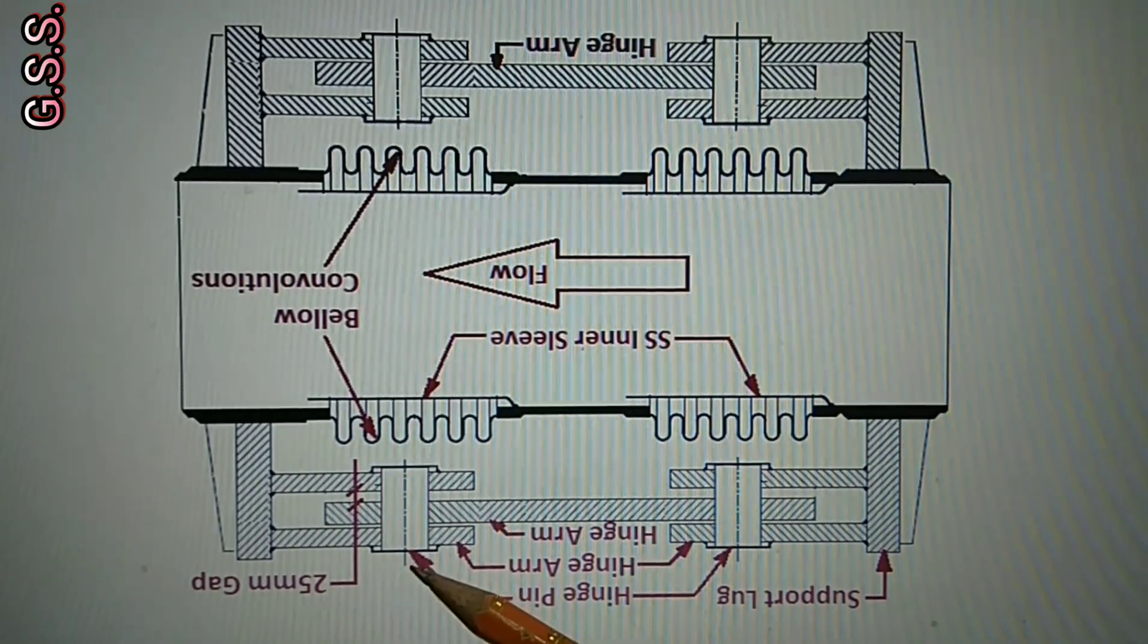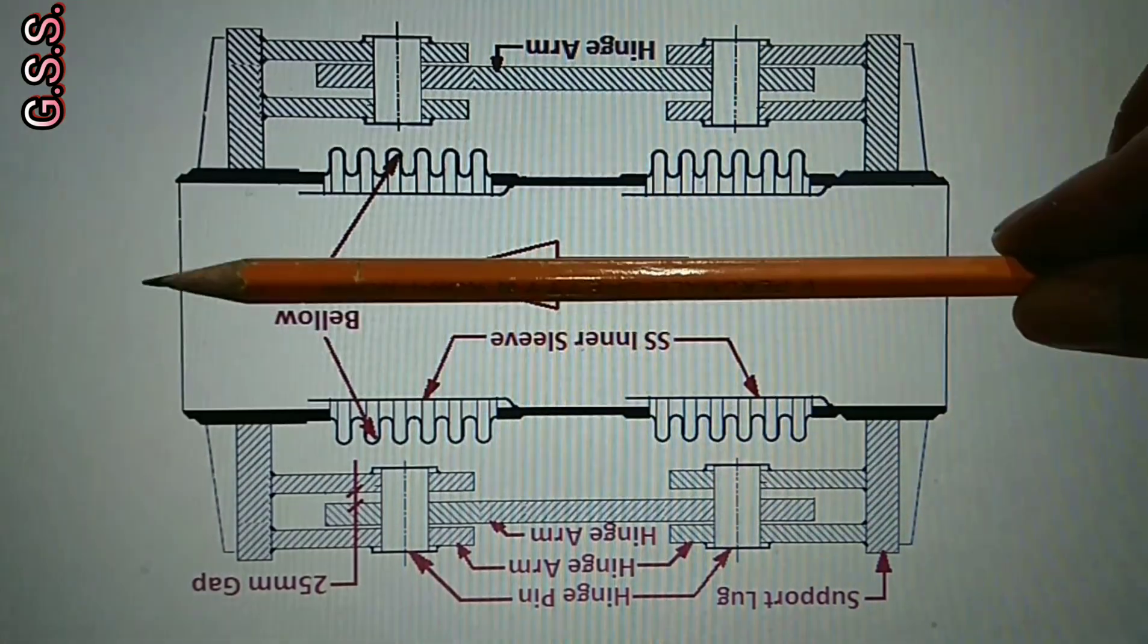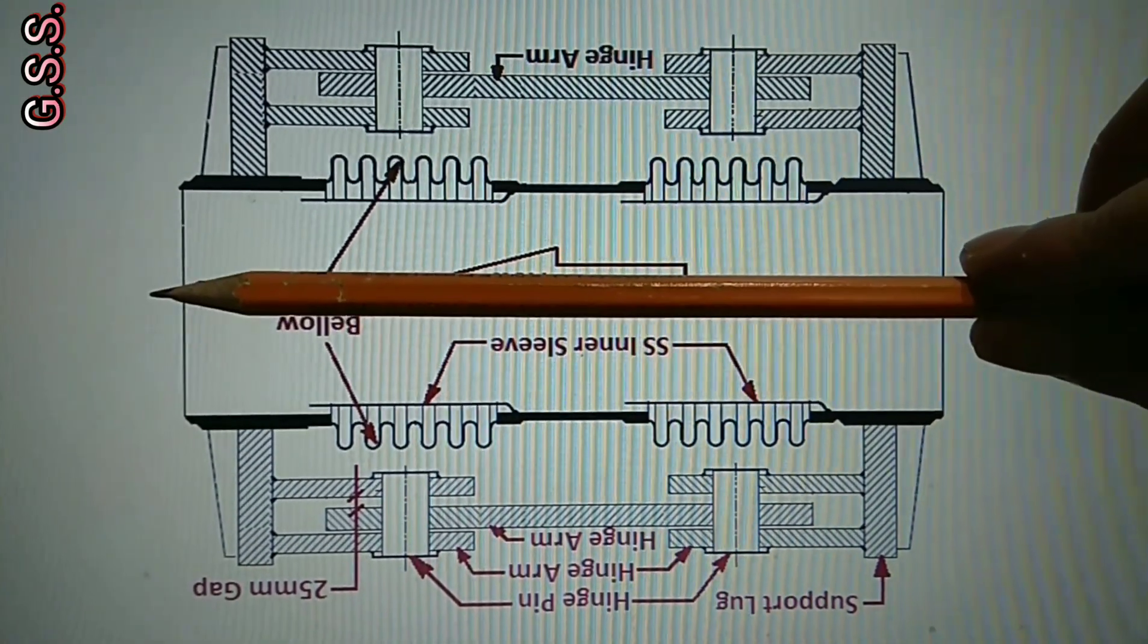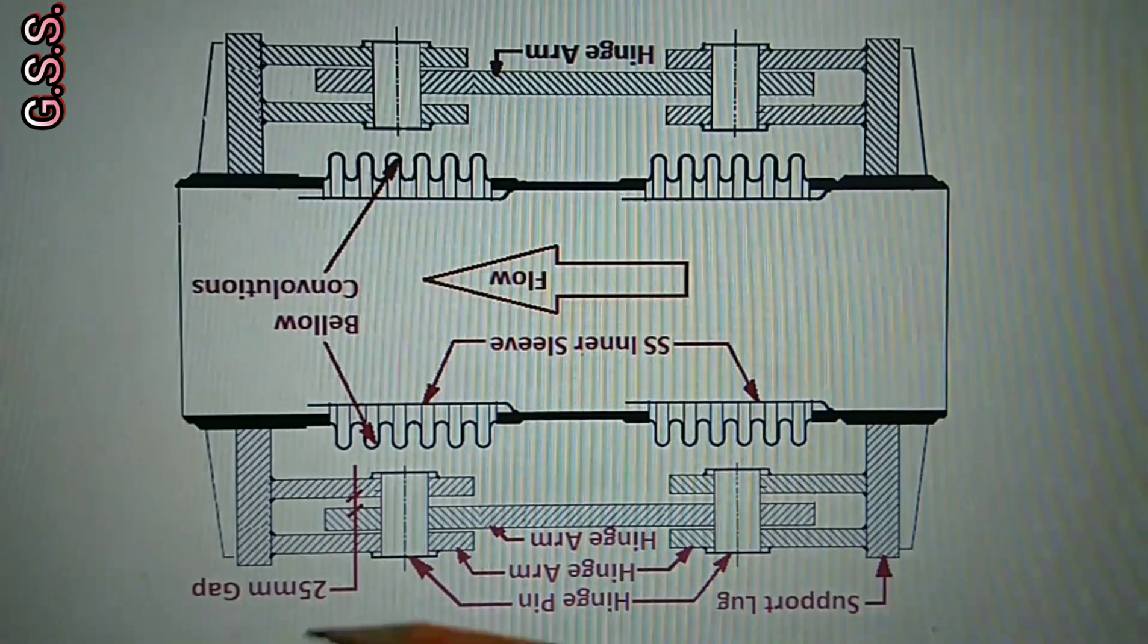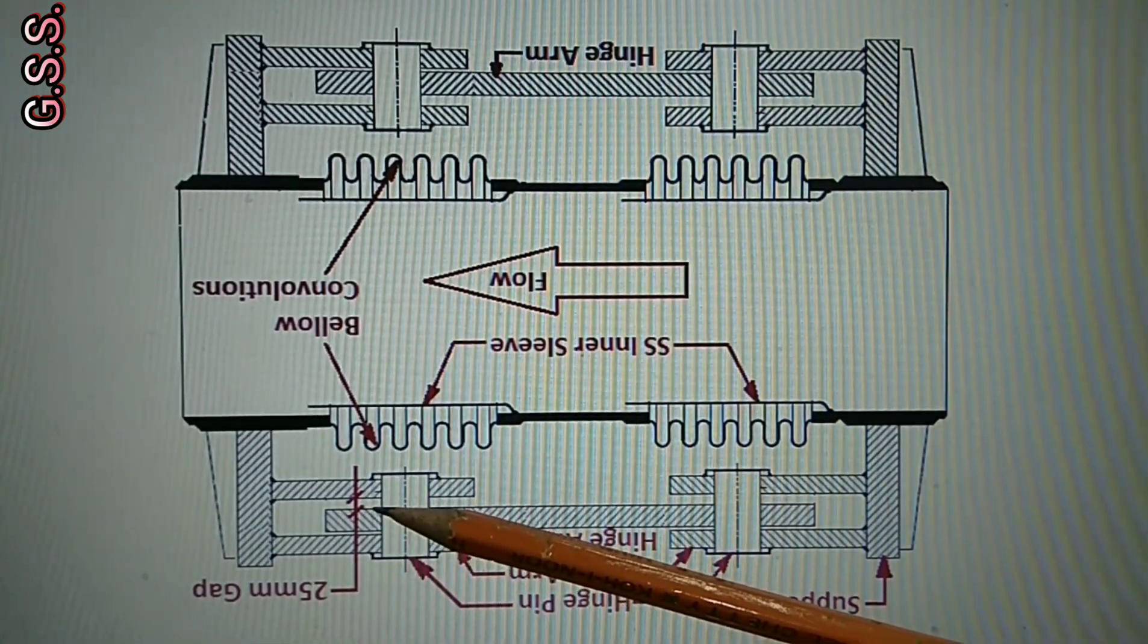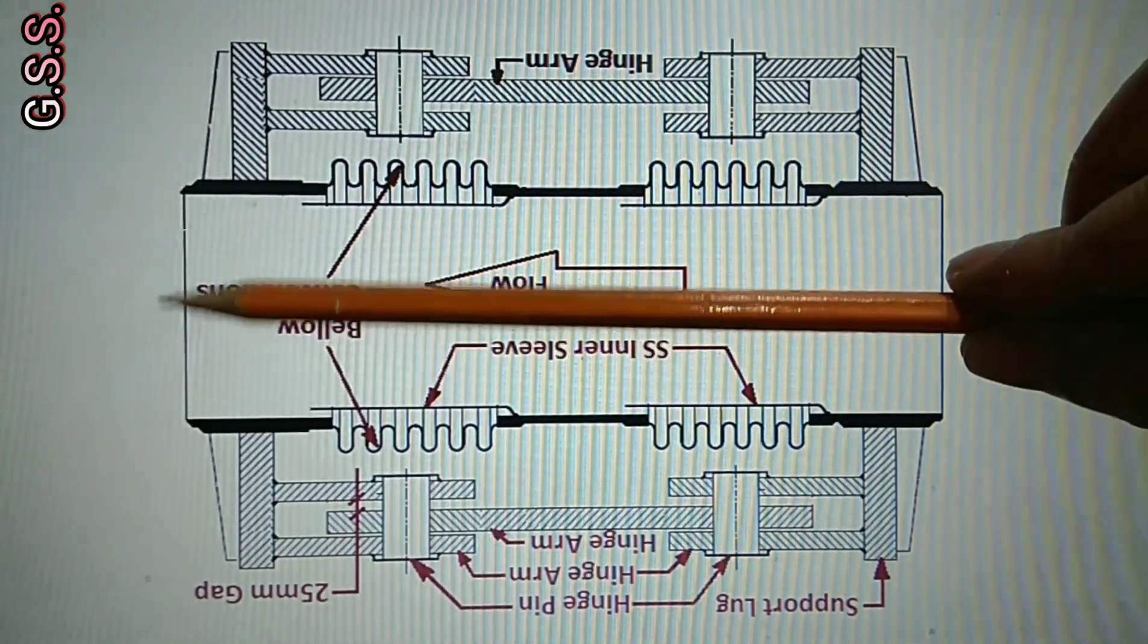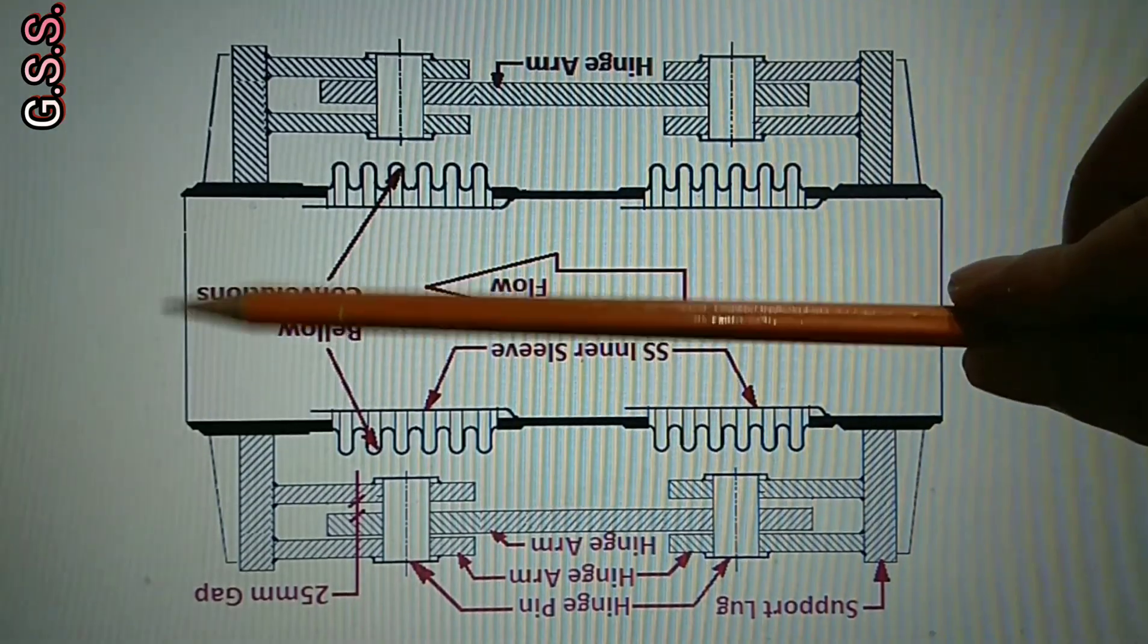The hinge pins allow the bellows to take lateral movement perpendicular to the hinge arm plane like this. And in between hinge arm a gap of about 1 inch is there which allows the bellows to take lateral movement along the hinge plane like this.